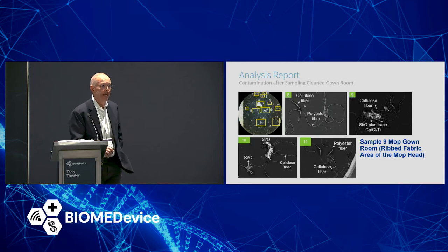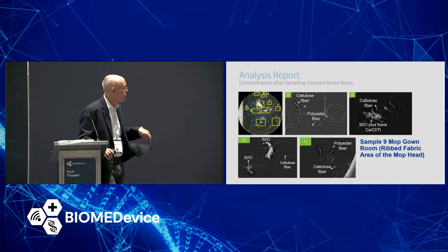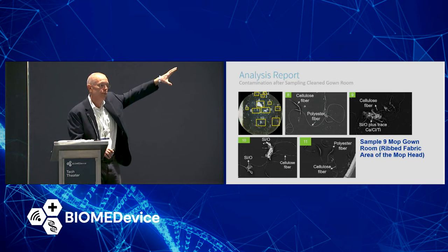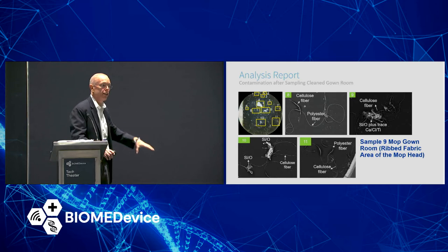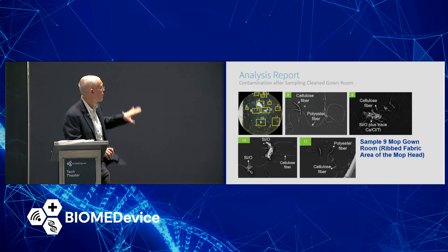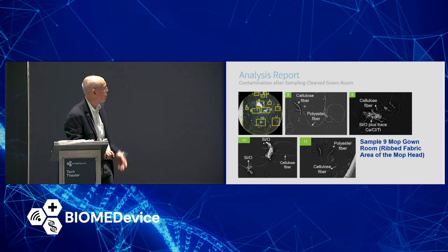While the clean room gowning industry does a fantastic job, we have found very few examples of contamination coming from rewashable clean room gowns. But where clean room gowns are a vector, if you will, is when you have one clean room, like a control room or an ISO 9 room, that shares a change room with your ISO 7 and ISO 5 rooms. All of the garments in the change room will be contaminated from the lower level clean rooms. We routinely wipe down the sleeve of garments for sampling, and this is what we find on the garments.